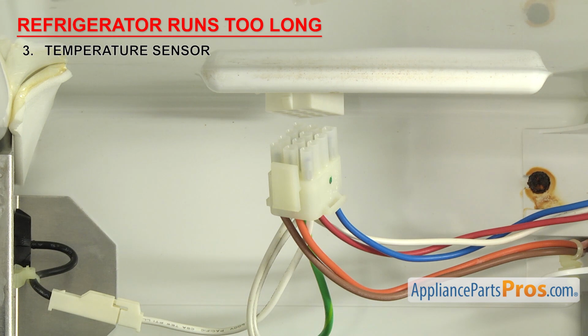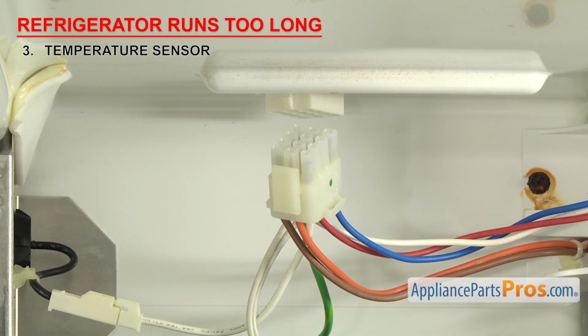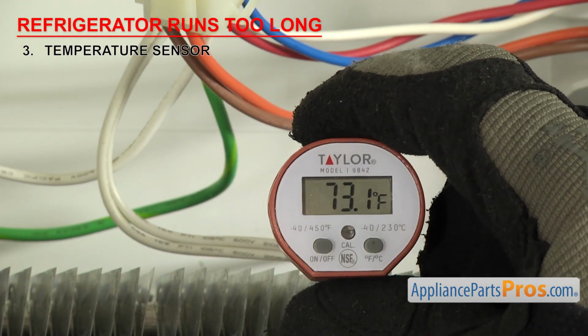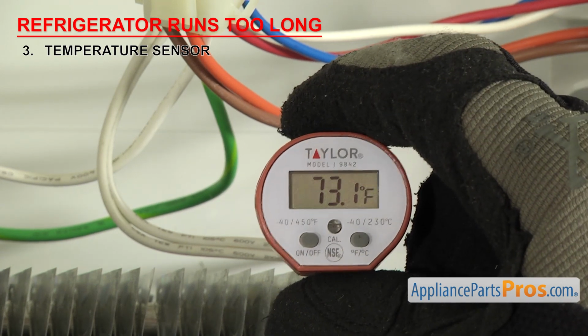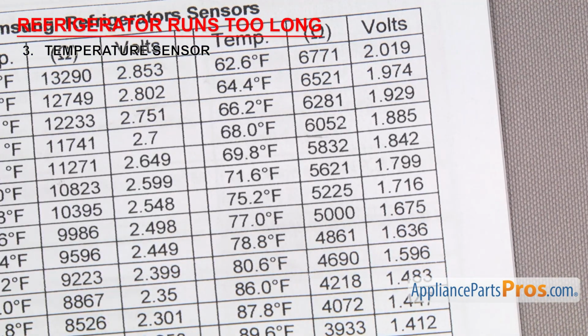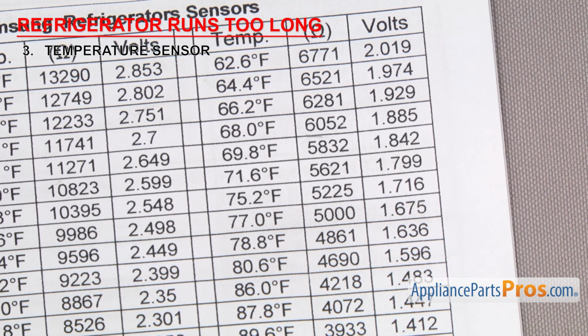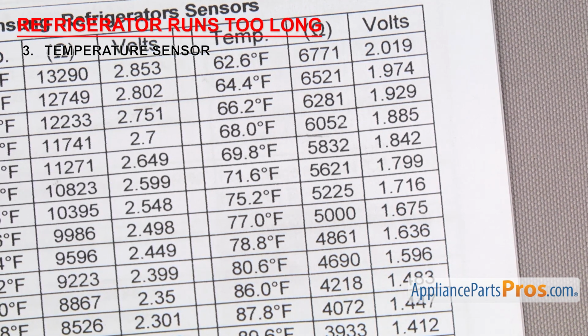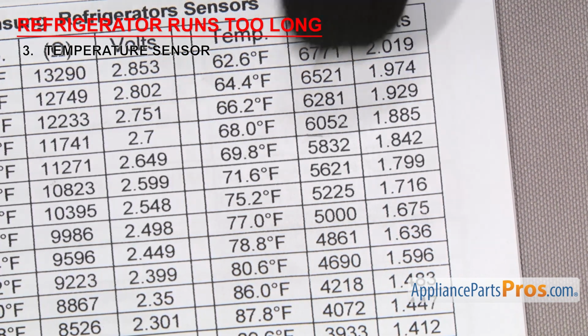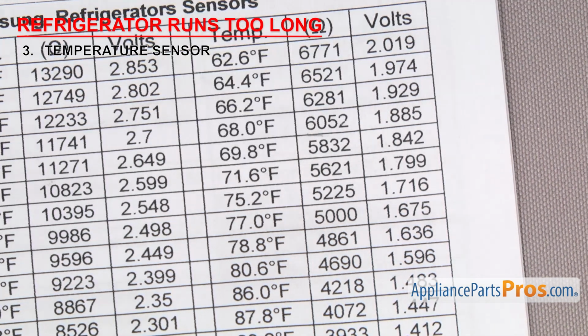As long as you have access to the plug or the bare wires, you may just be able to leave it in the fridge for testing. Once you're ready to test it, you need to check the ambient air temperature. In our case, it's about 73 degrees Fahrenheit. The sensor will have a different ohms reading depending upon the temperature, so you'll have to look at your tech sheet again to see what it should read. Our sheet says about 5,400 ohms at 73 degrees Fahrenheit.